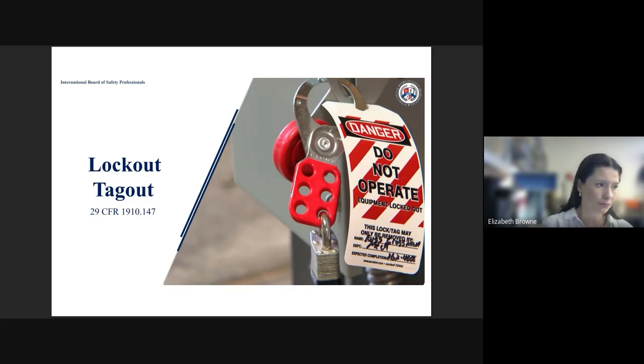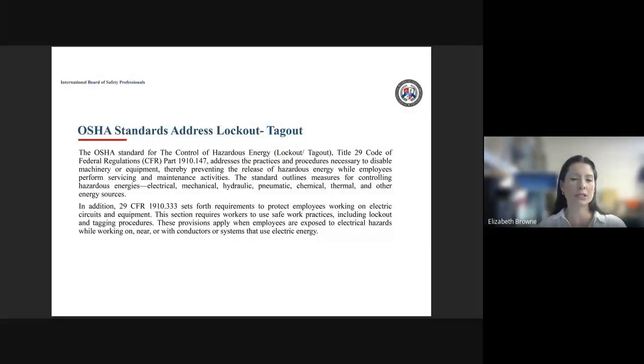And this is a very long-standing and commonly cited standard that OSHA finds very important and very necessary. And that is controlling hazardous energy sources. And that is found in 1910.147. And so we commonly call it lockout tagout, but the actual name of that standard is the control of hazardous energy, or like I said, lockout tagout. It is designed to prepare practices and procedures that disable equipment or the flow of electricity or any other hazardous energy to the equipment so that it prevents the unexpected release of that hazardous energy while an employee is performing maintenance, repairs, or servicing equipment.